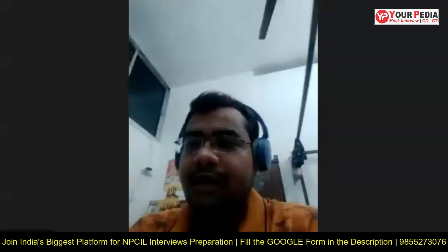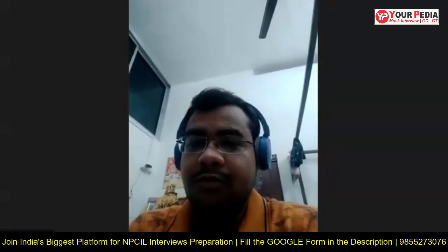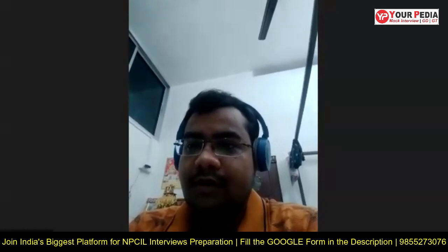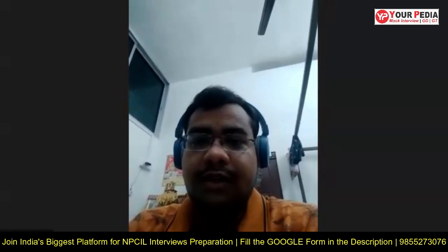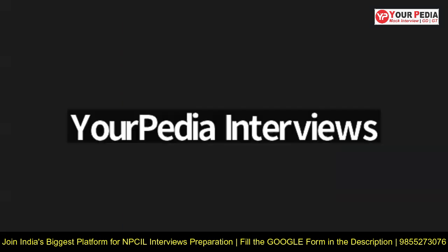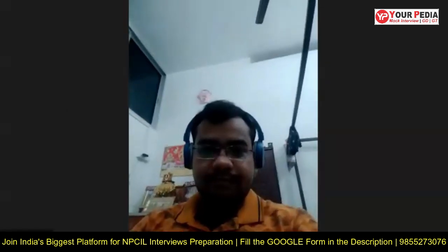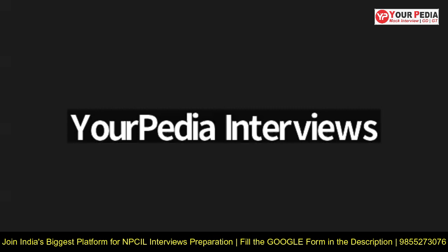Actually, testing is of two types: routine test and type test. Routine test is done on... I am asking, if we have some equipment, and if we are designing some equipment for a certain case, then it should be tested in the laboratory. So how do we generate that amount of voltage, like lightning, in the lab, so that the lightning arrestor can be tested?